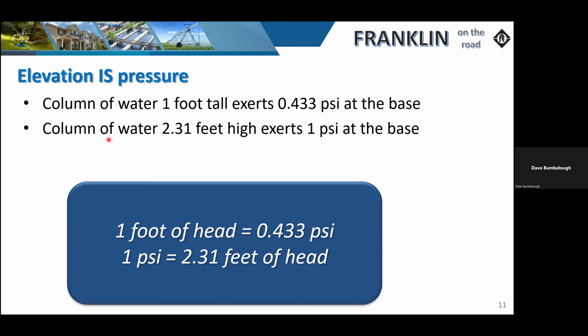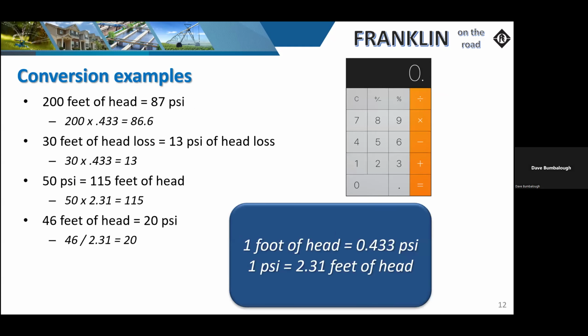Now, the conversion that I use the most is 2.31, and I'll show you in a couple exercises in the next slide. But as we look at this, basically 2.31 feet of water, if we were to measure at its base, we would see that it equals 1 psi. And that's the most common conversion that I use, as we'll see in this exercise. So if I was to take 200 feet of head, basically multiply that by 0.433, I'm going to come up with about 87 psi. So that's one way of using the 0.433. The ones that I use the most are basically the two bottom calculations here. So if I've got 50 psi on my gauge, that's equivalent to about 115 feet of head.